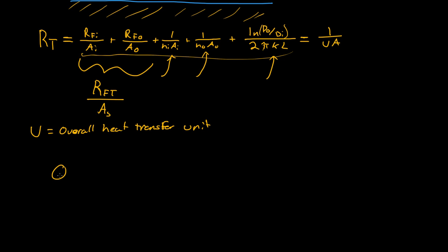We calculate that by knowing the total heat transfer. If we know the total amount of heat transferred across the system, which is Q, then Q equals the overall heat transfer unit times the area times the temperature between the hot fluid and the cold fluid. We can calculate Q where Q equals the mass flow rate of the cold fluid times the heat capacity of the cold fluid times the temperature difference of the cold fluid, delta Tc. Then we can get Q.